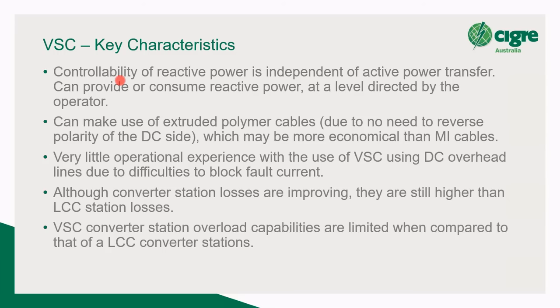I'll talk about that on the next slide. And although converter station losses are improving in VSC, they are still higher than LCC station losses. The vendors are talking about less than 1%. I've heard numbers like 0.8%. So the losses are getting down. And VSC, just by way of the equipment being used, can have less overload capability when compared to an LCC system. But it really depends on what type of module you've purchased, how much current overhead you have in your VSC submodule.